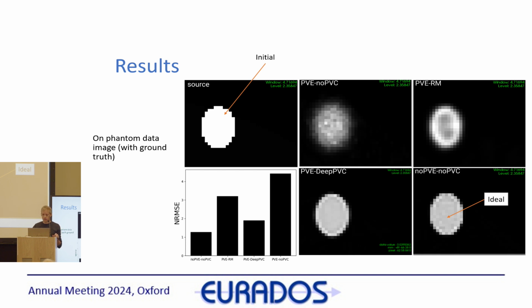This center image shows what you obtain straight from the SPECT imaging system if you don't correct for the partial volume effect. So it's very blurry, and if you make quantification here, you can obtain large uncertainty. On the right, this is what is usually obtained from a conventional commercial system with resolution modeling correction. It corrects a lot of this blurring effect, but still gives birth to ring artifacts with a very large hyper signal on the boundary of this ellipsoid sphere.